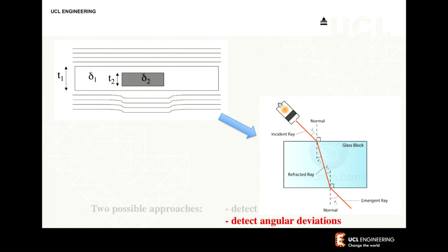You have to create some mechanism that enables you to pick up angular deviations on the order of a micro-radian. To demonstrate: traditionally, you're trying to distinguish the brightness of one spot from another by how much light is absorbed — which can be quite difficult if the attenuation difference is small. What we are doing instead is shining the same light through interfaces between objects, and then detecting the massive deviation of the spot due to refraction. In visible light the angle is many degrees and easy to see; for x-rays the angle is tiny, but the same ratio between the intensity of the effect applies.